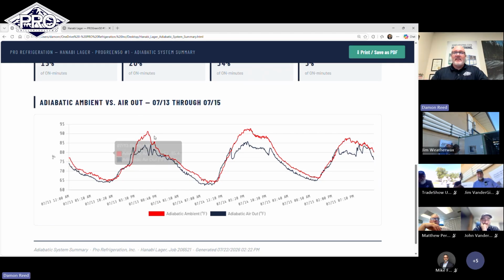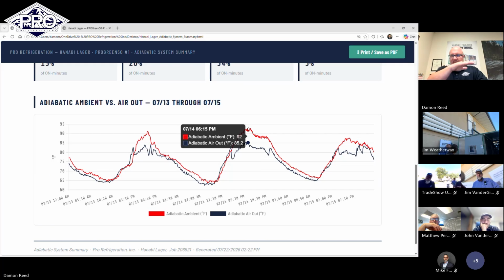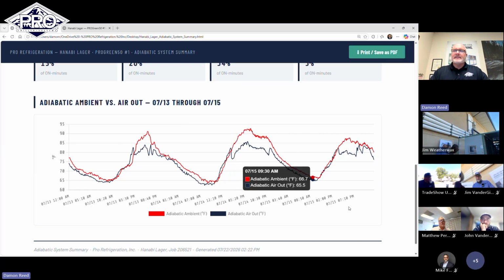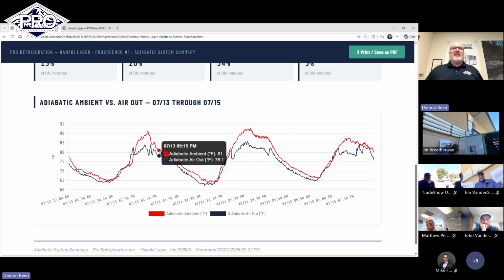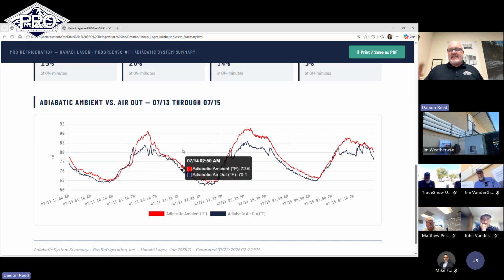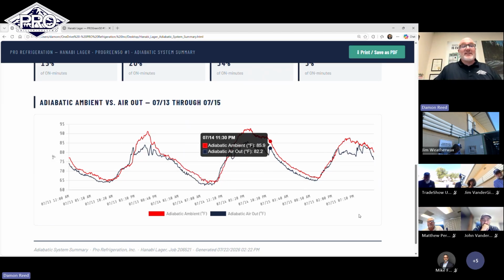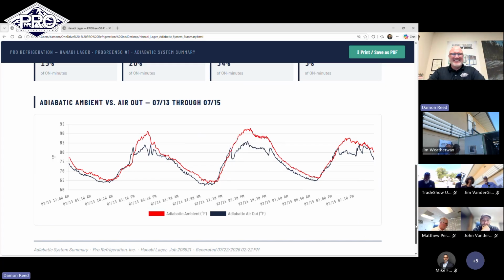So even though we were getting up into the 90s on ambient air temperature, mid 90s, I think I was seeing, the gas cooler saw 81 degrees the entire time, roughly, or cooler. Where it drops off at 85 ambient, we disengage the adiabatic, but you still have wetted surface. So you still get some adiabatic effect as it, let's call it uncharging, drying out the pads.